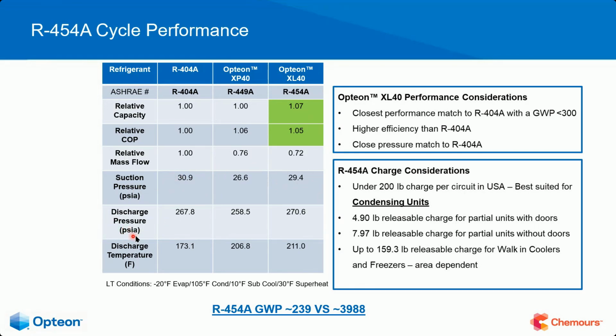Now on the discharge pressures, again, this is PSIA, not to make a big deal out of it. If you're seeing 267 on the high side, you'll see 258 on the 449A, and then 270.6 on the R454A. And again, this is absolute. So if it was gauge pressure, you would just think in your head minus around 15 or 14.7. Discharge temperatures, this is 6 inches out from the compressor. We're always focused on that. We never want it to be over the 225 mark if we can help it. All right. If it is designed to run over 225 degrees Fahrenheit, you can bet yourself that it has some kind of OEM thermistor or some way to read temperature just beyond that 6 inches. And that's when we start to see our liquid and vapor injections.